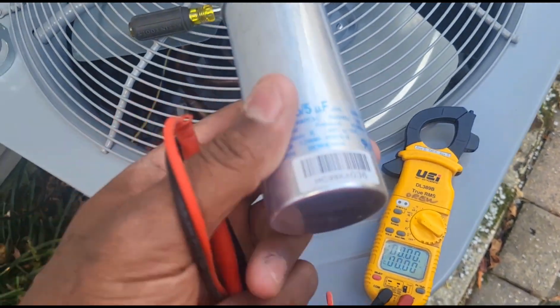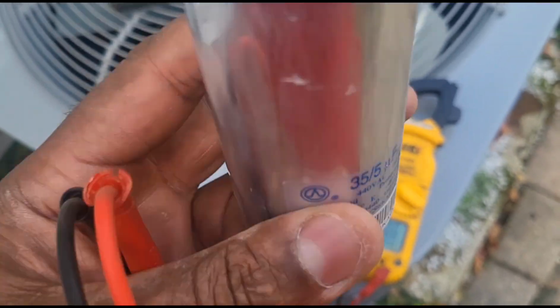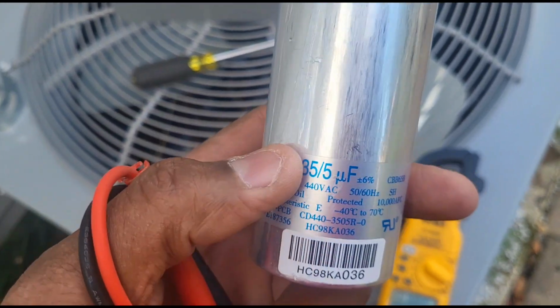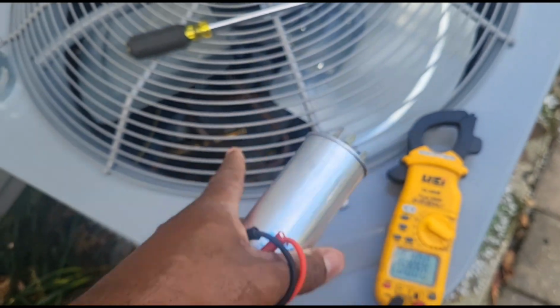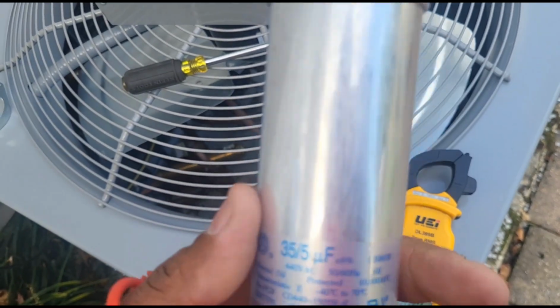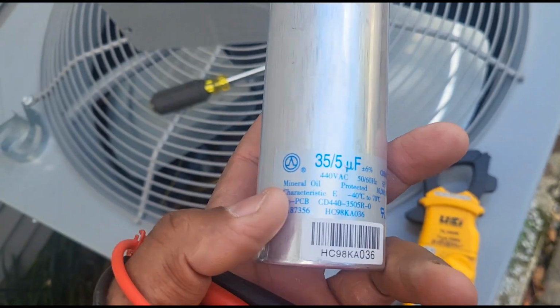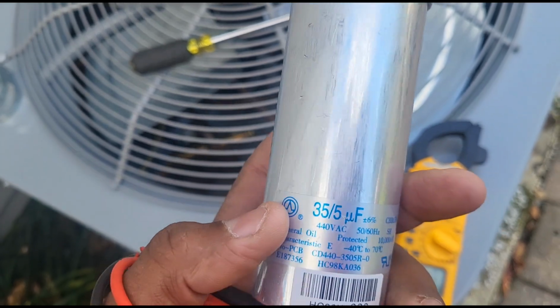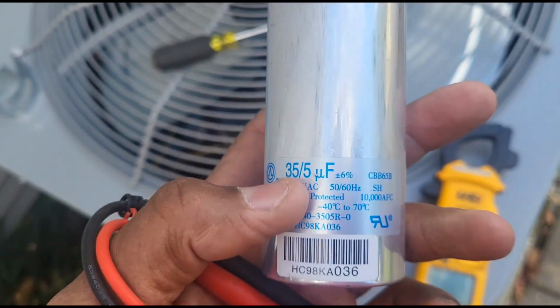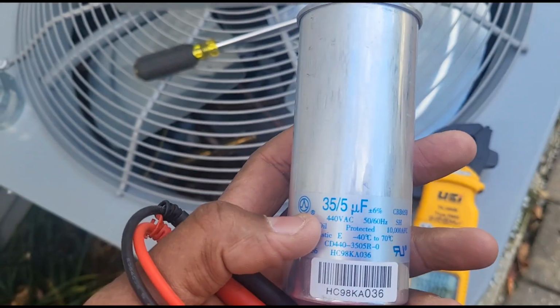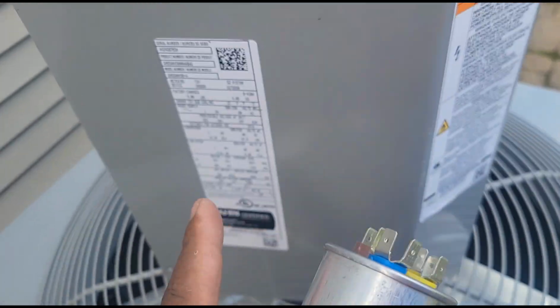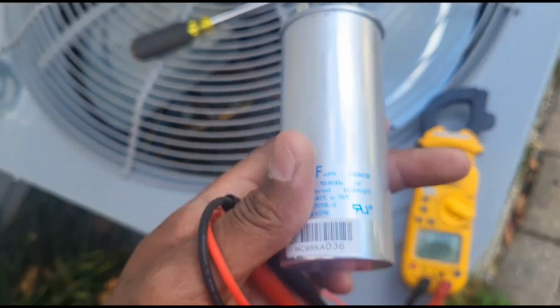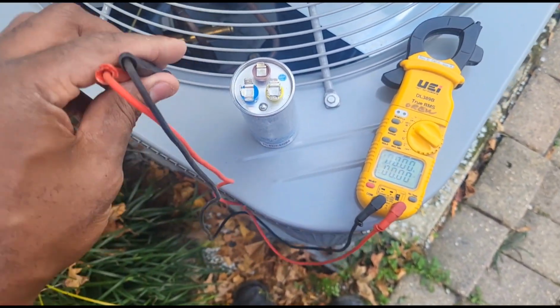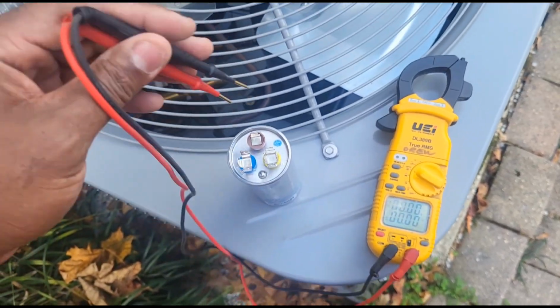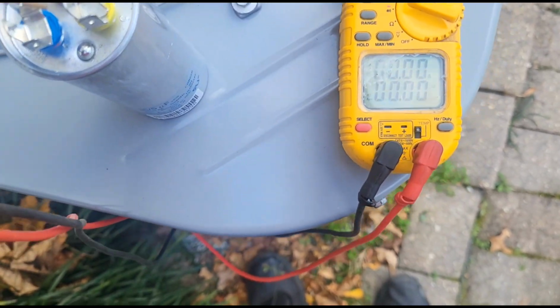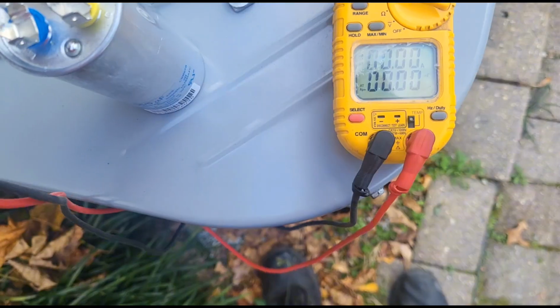Remember, like I mentioned in previous videos, even with newer heat pumps, this capacitor gets used year-round since this heat pump does both heat and AC. So even if I told you before that within 3 years you're not going to have much wear and tear on most typical dual caps, that could vary with heat pump capacitors, being that this is a 2024 model. It wouldn't surprise me if the numbers were a little lower than normal, since this is a year-round item to be used.